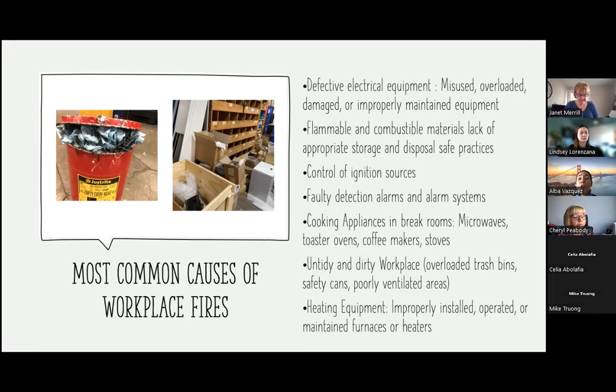Faulty detection alarms and alarm systems. Many times you come into a building you're renting or leasing, and the equipment, detection alarms, alarm systems, and pull stations are not properly maintained. You must do due diligence for those things to be kept up, and you have to have records of the maintenance, because for pull station alarms, a lot of the recommendations are for a visual inspection every 6 months, and actually testing the alarm at least once a year.